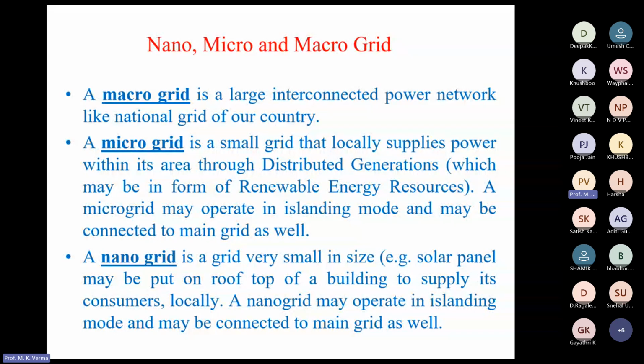Say, for example, your Allahabad city or your campus, with renewable energy resources. So this is called a microgrid. The microgrid can operate in isolation or it may supply to the main grid, depending upon requirement and availability of power. A nanogrid is a further smaller grid, very small in size. For example, we have an apartment and we put solar panels on the rooftop, and it locally meets the demand of the consumers in that building. So that is the nanogrid. Similar to a microgrid, a nanogrid can also operate in islanding mode or it may be connected to the main grid.